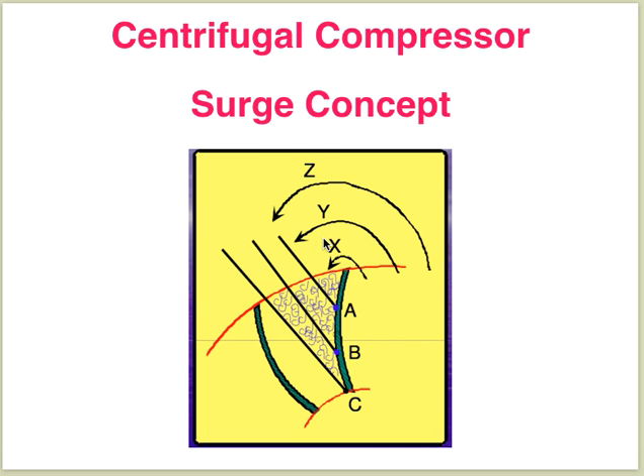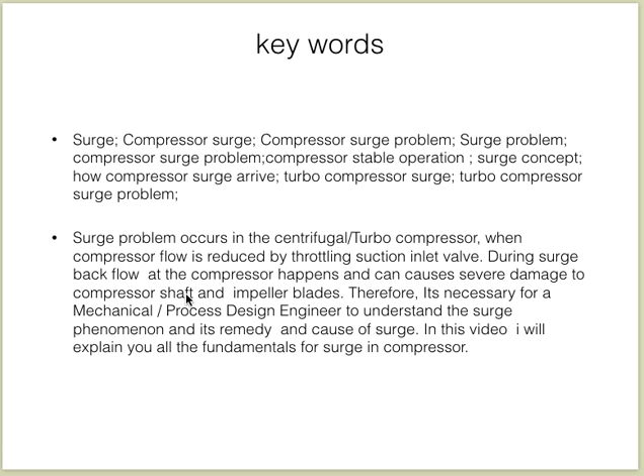Today we'll discuss the centrifugal compressor surge concepts. This picture depicts the surge or backflow in a centrifugal compressor. Surge occurs in centrifugal and turbo compressors only when the compressor flow is reduced by throttling the suction inlet valve. During surge, backflow at the compressor happens and can cause severe damage to the compressor shaft and impeller blades. It is necessary for a mechanical and process design engineer to understand the surge phenomena, its remedy, and cause.